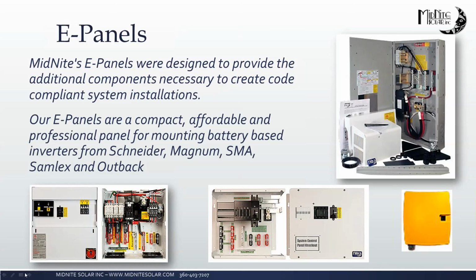Anything you'd like to add to that, Ryan? You pretty well covered it. I mean, it's basically a complete balance of system. It gives you all your AC bypass, your overcurrent protection, room for expansion with all of that in a very code-compliant manner. And as you said, we really do make them look like they belong together. The Schneider stuff will be painted color match to match the inverters. The SMA, as you see, is a molded plastic door to match the Sunny Island. So we take a lot of pains to try to make that look like it belongs together.